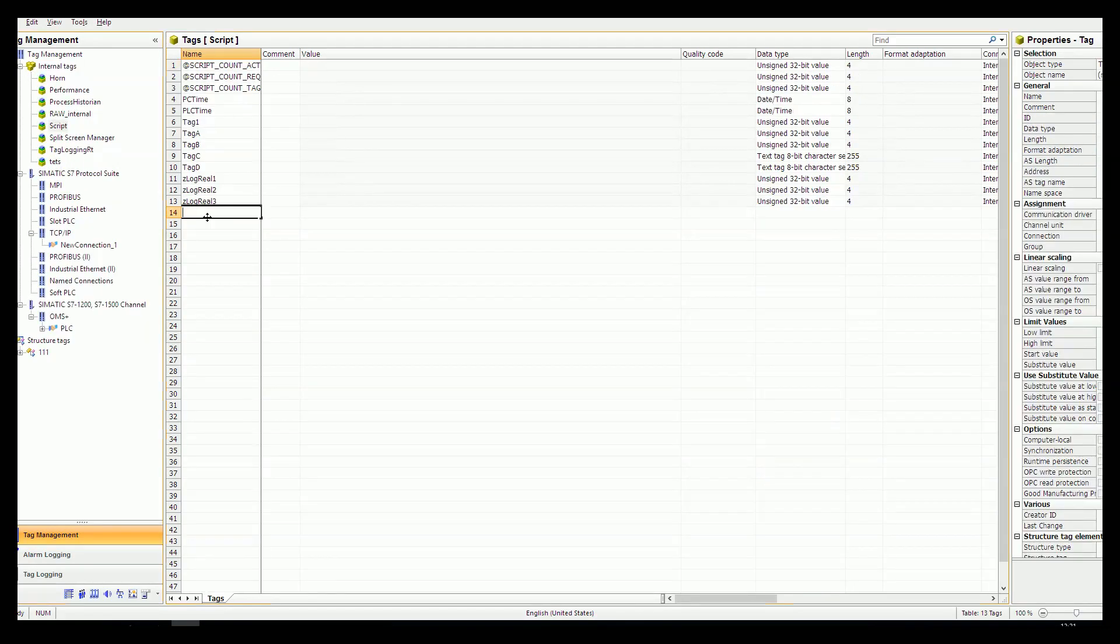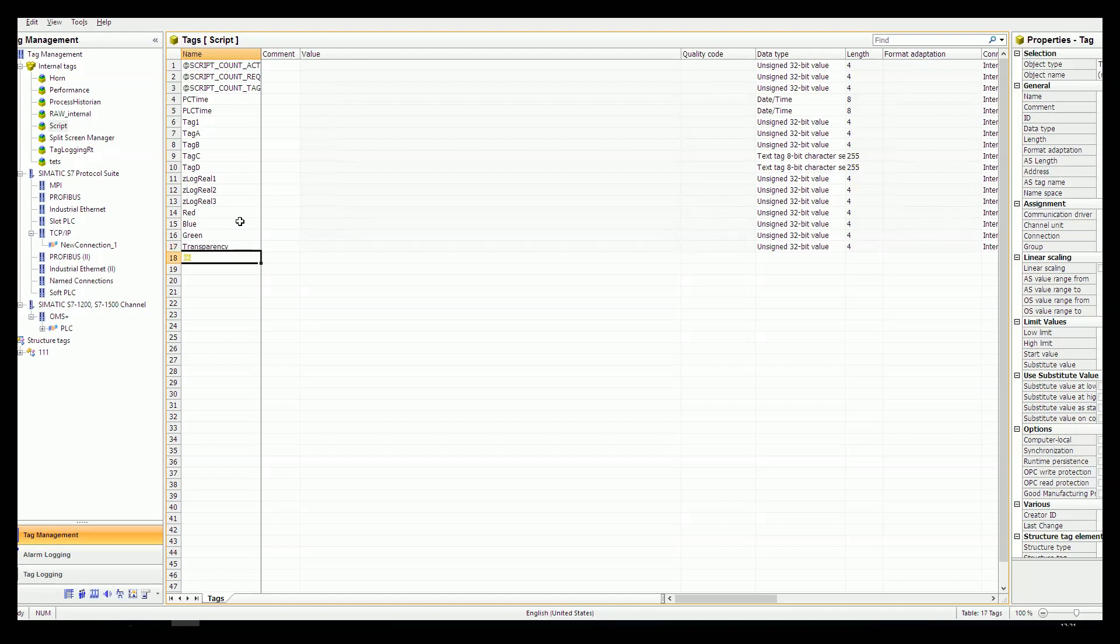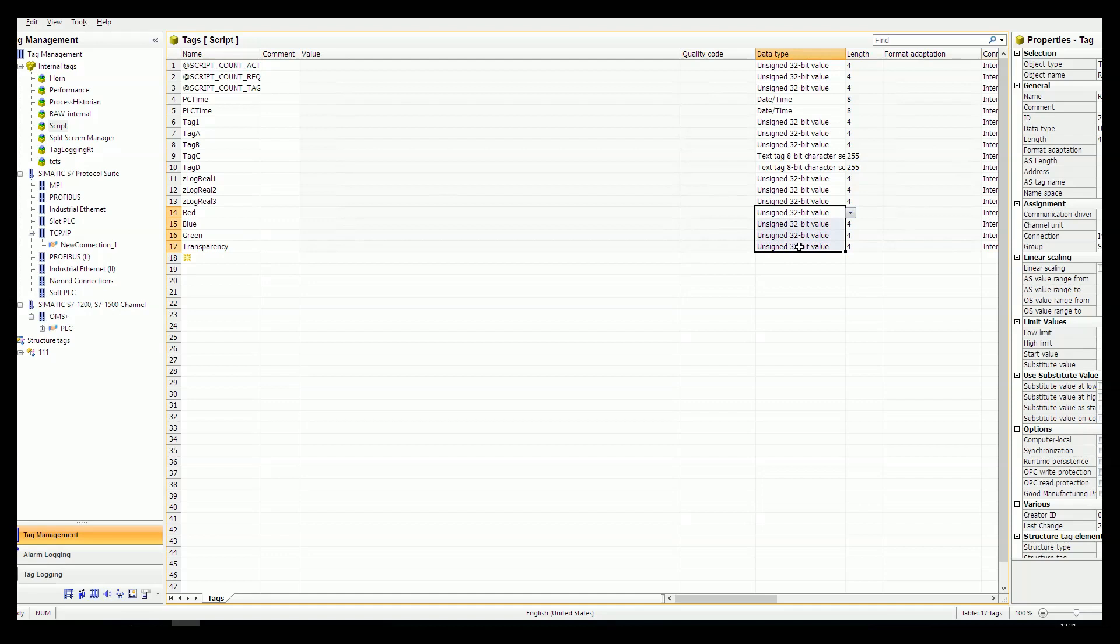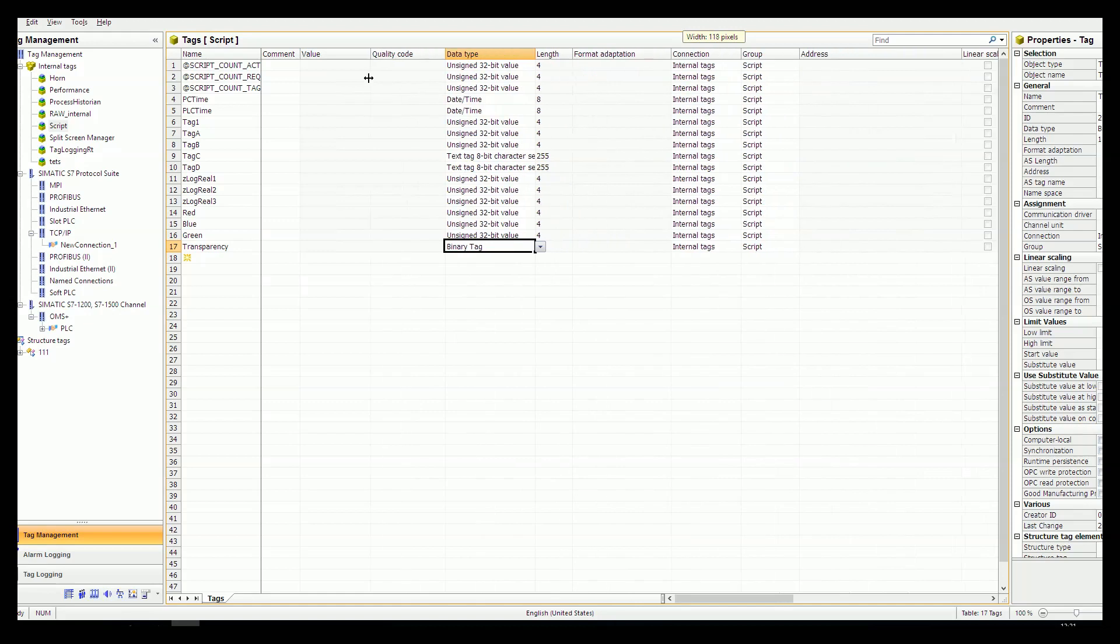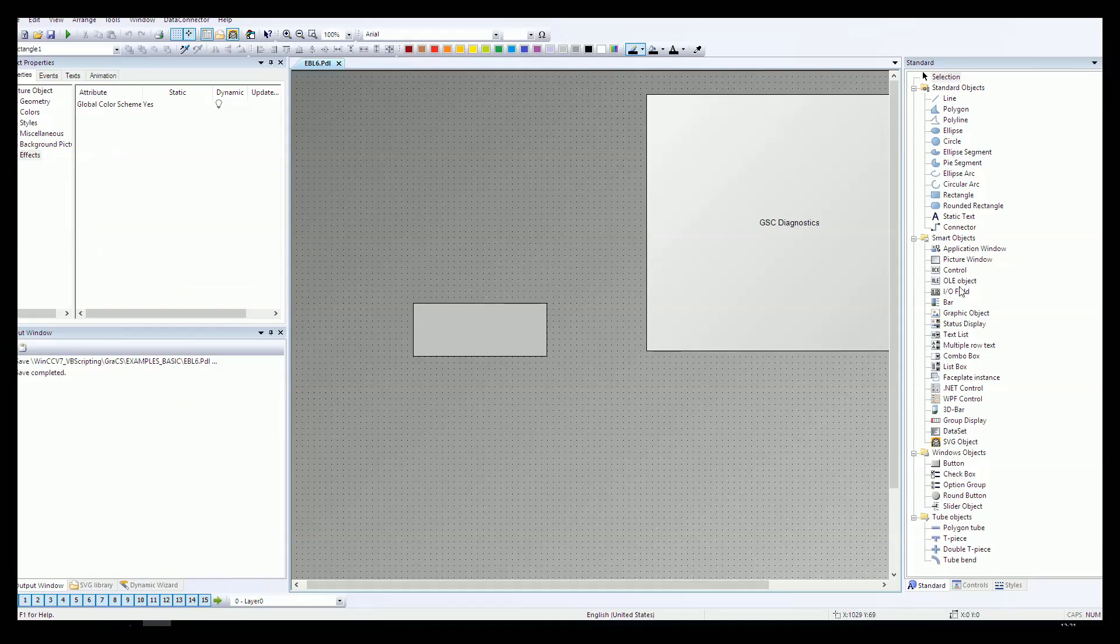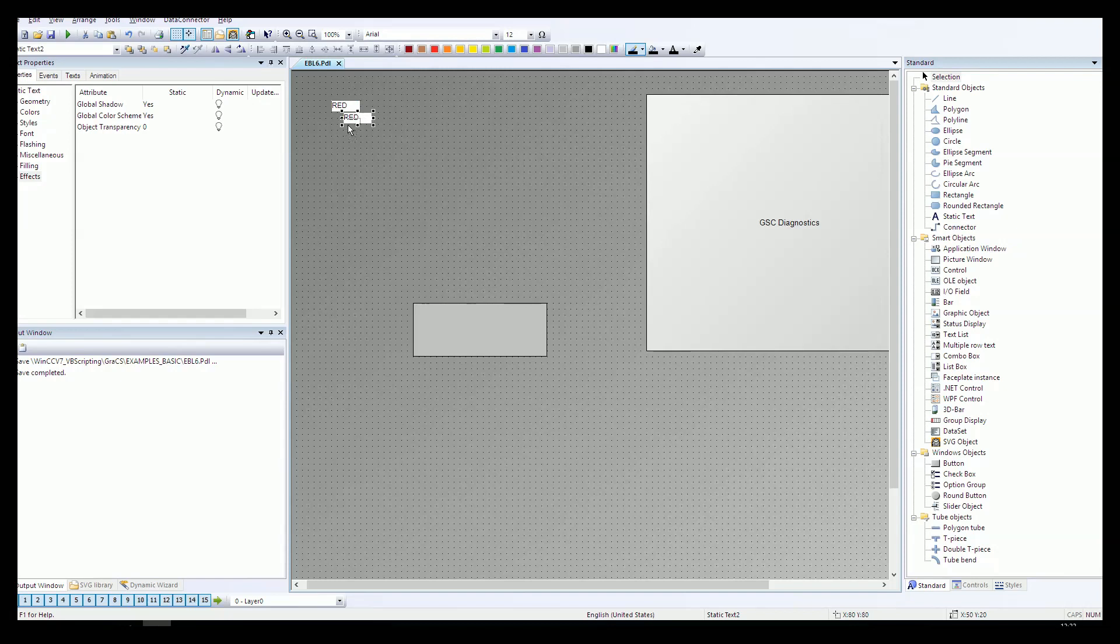I can make this on the screen and change it dynamically while running, so I can modify this during WinCC runtime. These could also be PLC tags. Both will be unsigned 16-bit integers, which should be enough. We could also use binary tags, but I think we can set up the dynamization with transparency from 0% to 100%. Let's put red, blue, green, and transparency on screen.